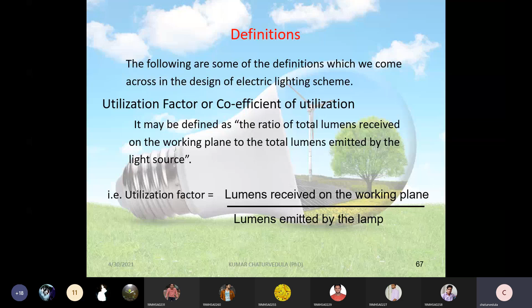Utilization factor is affected by some factors like the type of light fitting, so what type of light fitting you are using, then the color of surfaces and ceilings. You are going to give different colors to different walls, and you can see so many decorations on the ceiling. So depending on the colors you choose for the surface walls, and the type of ceiling you choose, this utilization factor will vary. Then the mounting height of the lamp, that is, at which height compared to the working plane you are placing your lamp, and the area to be illuminated. All these parameters affect the utilization factor.